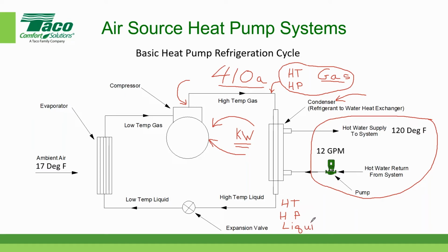Doesn't liquid take a U though? L-I-Q-U-I-D? Yes, you did. Okay. So this is one of the magic things about refrigerant. And in order to change that from a gas to a liquid, we have to remove energy. And when we do that, in this particular case, we're circulating roughly 12 gallons per minute of water through this refrigerant to water heat exchanger. And usually this is a brazed plate heat exchanger. So we're going to circulate water in here, and when the water enters, it's probably close to 110 degrees. We'll just say it's 110 degrees.